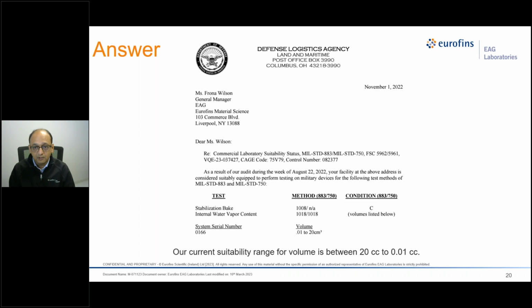Now, the technical part is that we have two constraints here. First, I need to have a volume calibrator that can provide me a volume in the required range. So if we have to move out of this range, I need to build a special volume calibrator, which is probably the easier task. The more difficult task, going back to the signal to noise ratio, is this: if I put in a low amount of gas, can I still maintain a signal to noise ratio above 20? If I can do that, then I would be able to do a lower volume. So in that case, one has to consider the limitation of the instrumentation. But right now, to answer the question, we can do any cavity which is above 0.01 cc and less than 20 cc.